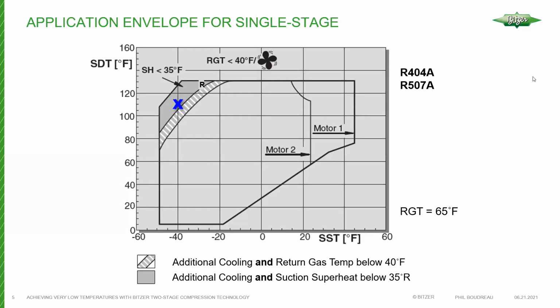So if we look at a minus 40 Fahrenheit saturated suction temperature and 110 saturated discharge temperature, we can see where the operating point falls on the envelope here for a typical single stage compressor. And you'll note that in that darkish gray area there, the note at the bottom of the page indicates additional cooling and suction superheat below 35 degrees Rankine. So 35 degrees above your saturated suction temperature would be the absolute max. And you would need a head cooling fan for sure. And in some cases you need liquid injection and a head cooling fan. So these are, of course, to keep the compressor cool and to keep that oil from burning up on us.